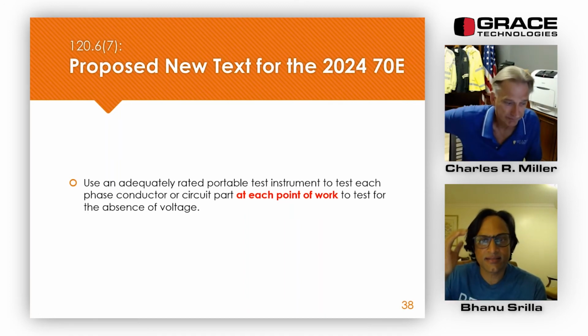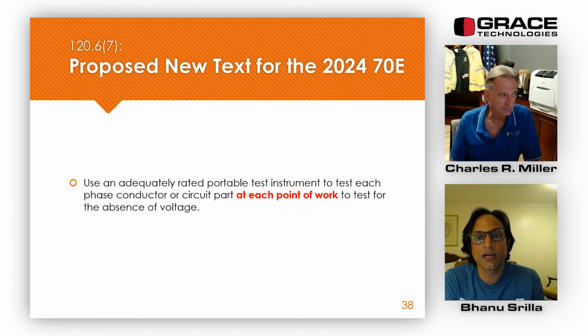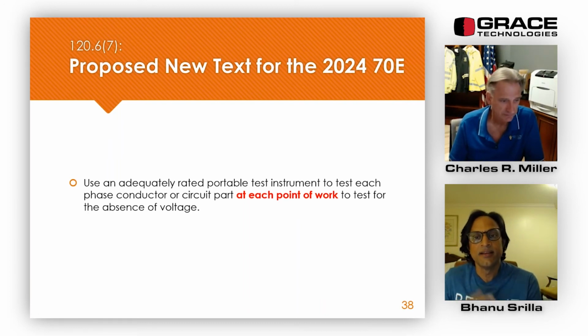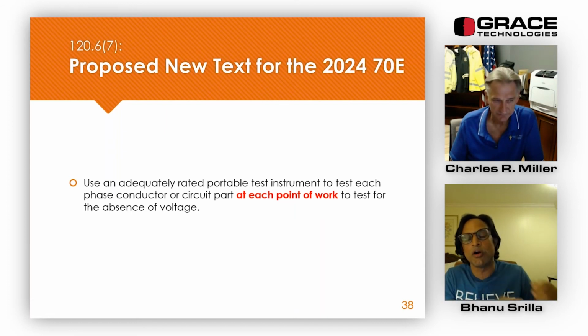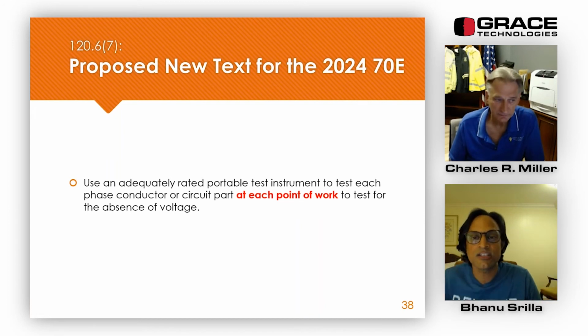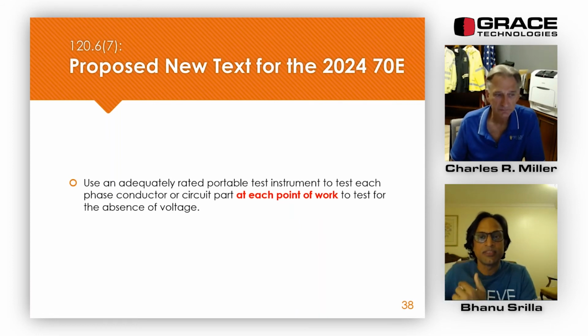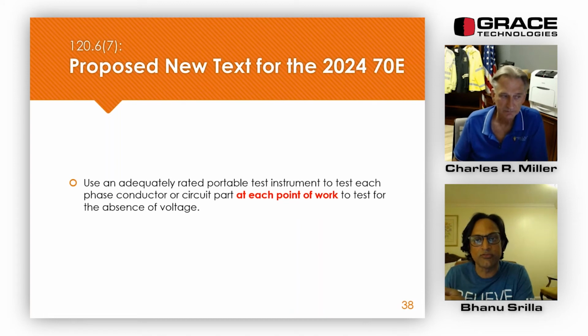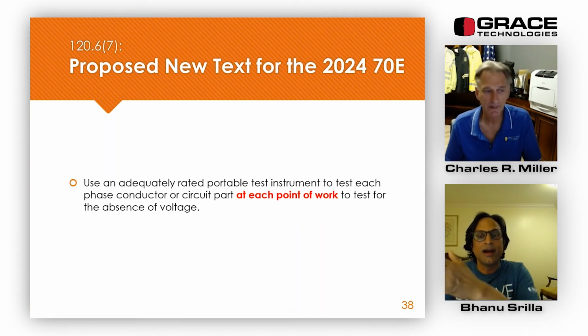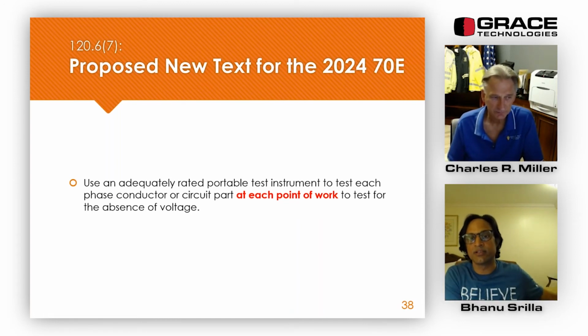Thanks, Charlie. I asked Charlie to specifically talk about this point in detail because it's going to make it very difficult for the people working in the industry to don complete PPE and test for absence of voltage at each point of work. As Charlie mentioned, take an example of an industrial control panel, which is generally used by most industries. They have a 600 volt or 480 volt incomer. They will disconnect it, verify the absence of voltage at the load side of the disconnect, and then they can keep working on the other side of the equation.